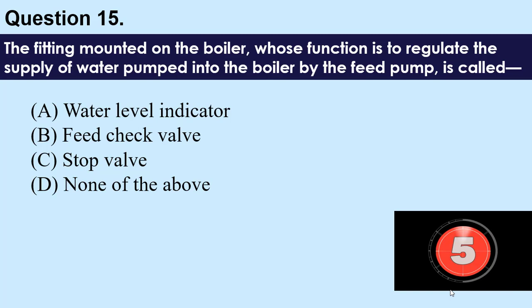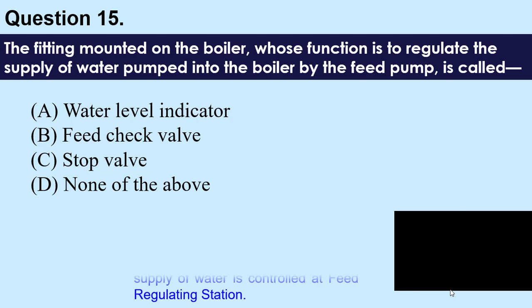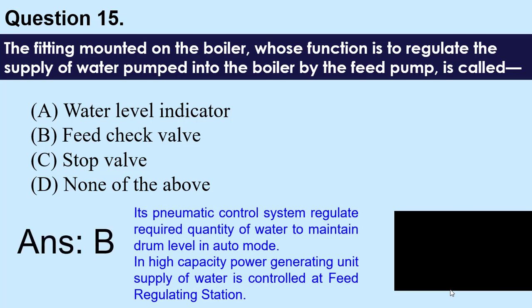Question number 15: The fitting mounted on the boiler whose function is to regulate the supply of water pumped into the boiler by the feed pump is called — A) water level indicator, B) feed check valve, C) stop valve, D) none of the above. The answer is B — feed check valve. Its pneumatic control system regulates the required quantity of water to maintain drum level in auto mode. In high-capacity power generating units, supply of water is controlled at the feed regulating station.